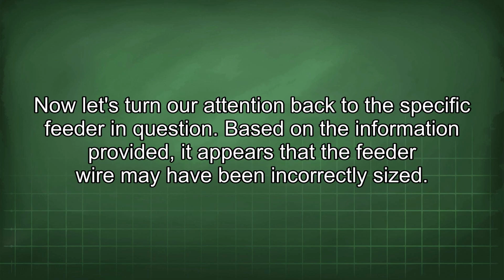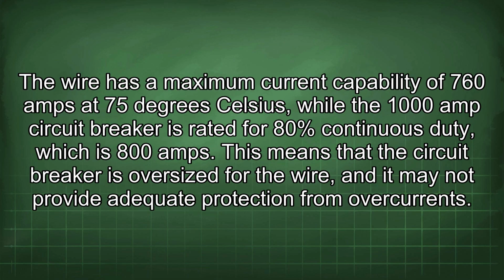Now let's turn our attention back to the specific feeder in question. Based on the information provided, it appears that the feeder wire may have been incorrectly sized. The wire has a maximum current capability of 760 amps at 75 degrees Celsius, while the 1000 amp circuit breaker is rated for 80% continuous duty, which is 800 amps. This means that the circuit breaker is oversized for the wire, and it may not provide adequate protection from overcurrents.